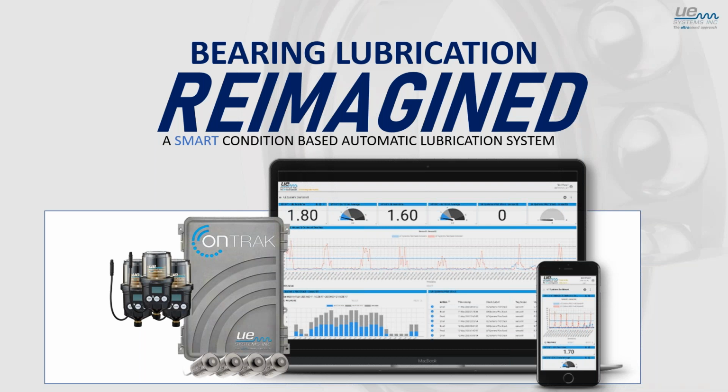All right, talk about harsh conditions, whether wet or extreme temperature. Yeah, I'm going up to the oil sands in northern Alberta in Canada, if anyone's familiar with it. From a human perspective, it's pretty rough, mining with the leach tanks and all this kind of stuff. The OnTrak itself is IP68 rated, indoor and outdoor. The OnTrak gateway typically gets mounted away from the process units. What I'm concerned about most is the sensor itself. Again, it's IP68. We can actually submerge them completely underwater, but they're completely stainless steel and epoxy filled, so water ingress is not an issue. So now we're looking at the resilience of the cable and things like that.